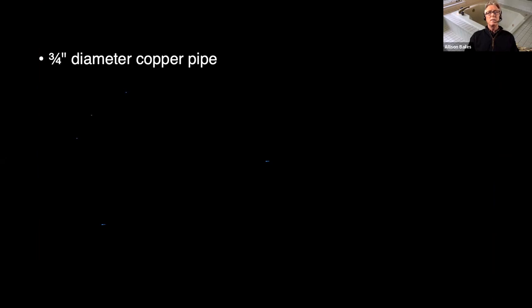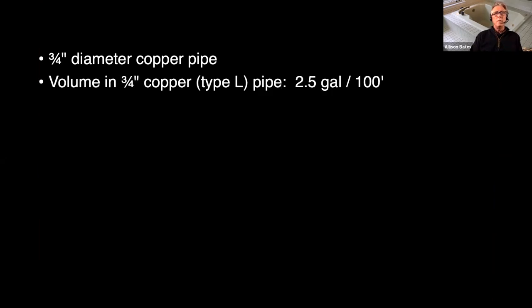So let's look at some details here. We've got a 3/4 inch diameter pipe, and the volume in there is about 2.5 gallons for every 100 feet of pipe. That means if I'm running 3 gallons into that bucket waiting for hot water to arrive, that would correspond to about 120 feet of pipe.